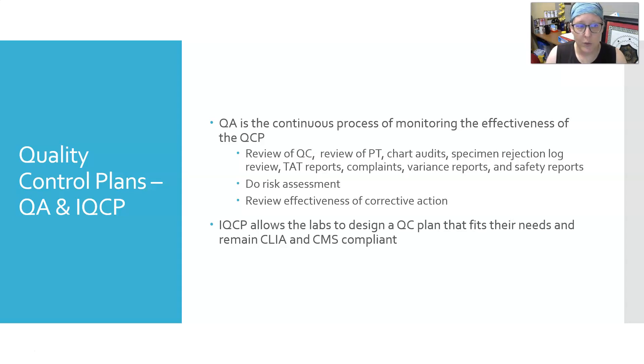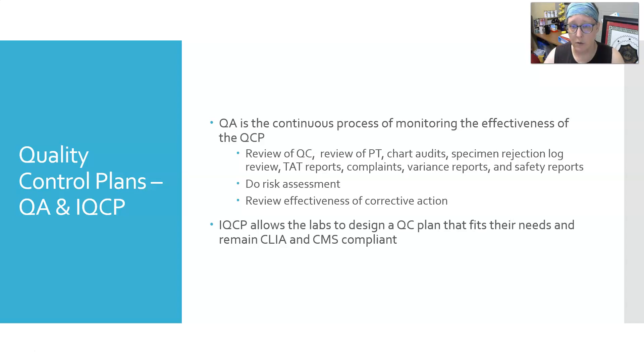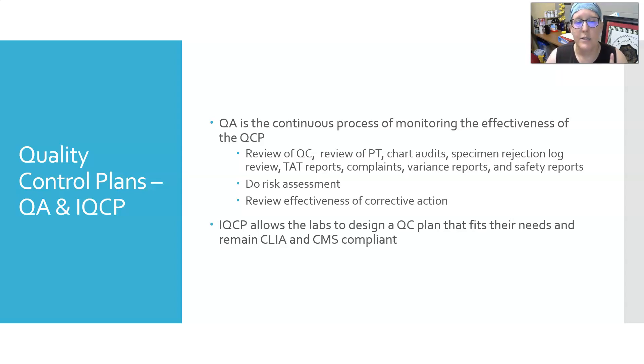QA, or quality assurance, is the continuous process of monitoring the effectiveness of the quality control plan. It can include the review of quality control on each analyzer, review of proficiency testing for each test, chart audits, specimen rejection log review, turnaround time reports, complaints, variance reports, and safety reports. Labs should do risk assessments to identify risks and review the effectiveness of any corrective action. The IQCP — Individualized Quality Control Plan — allows labs to design a quality control plan that fits their needs while remaining CLIA and CMS compliant.